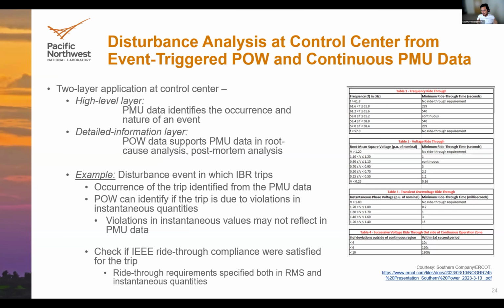As I mentioned, the occurrence of the trip can be identified from the PMU data. The point-on-wave data can identify if the trip was due to violations in the instantaneous quantities. So you can have instantaneous overvoltage that can lead to the trip. You can have instantaneous overcurrent that can lead to the trip. All these things might not be observable in PMU data. But if you have point-on-wave data available at your disposal, then you can dig in to understand what exactly happened.